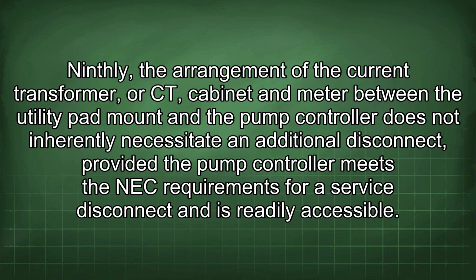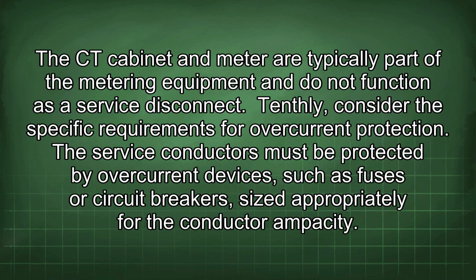Ninthly, the arrangement of the current transformer, or CT, cabinet and meter between the utility pad mount and the pump controller does not inherently necessitate an additional disconnect, provided the pump controller meets the NEC requirements for service disconnect and is readily accessible. The CT cabinet and meter are typically part of the metering equipment and do not function as a service disconnect. Tenthly, consider the specific requirements for overcurrent protection.